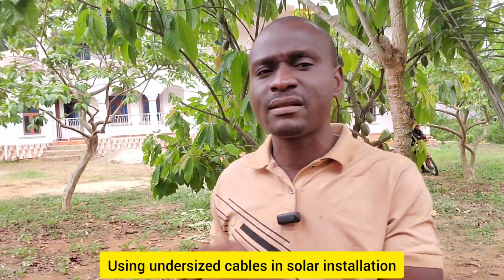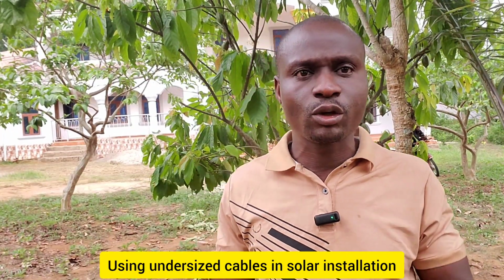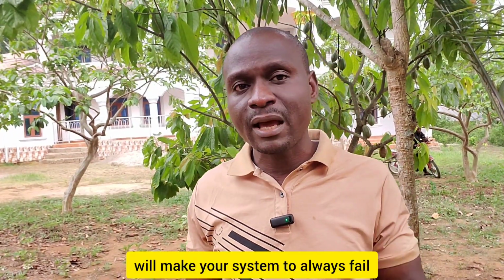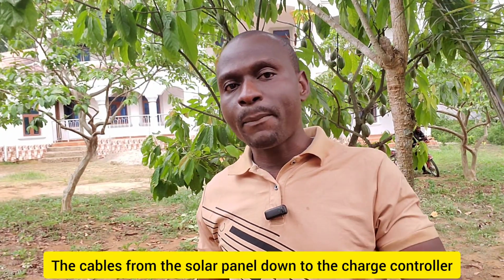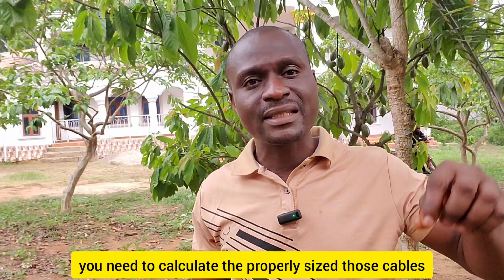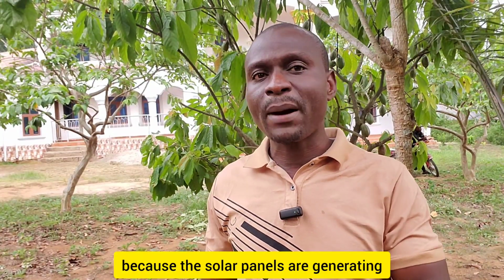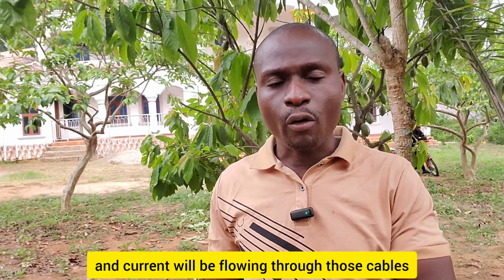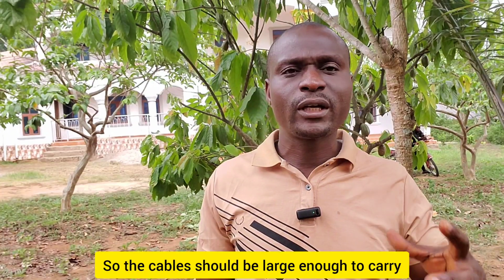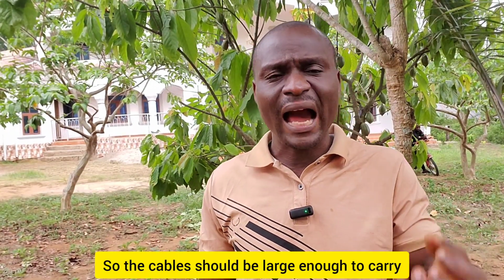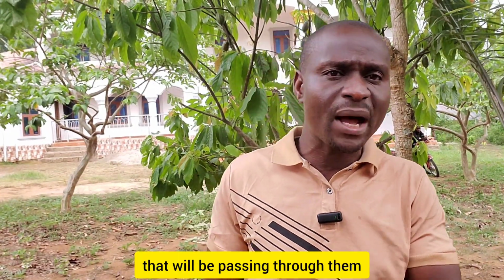Now, mistake number 5 is incorrect wiring and connections. Using undersized cables in a solar installation will make your system always fail. For the cables from the solar panel down to the charge controller, you need to calculate and properly size those cables, because the solar panels are generating and current will be flowing through those cables. So the cables should be large enough to carry the amount of current that will be passing through them.